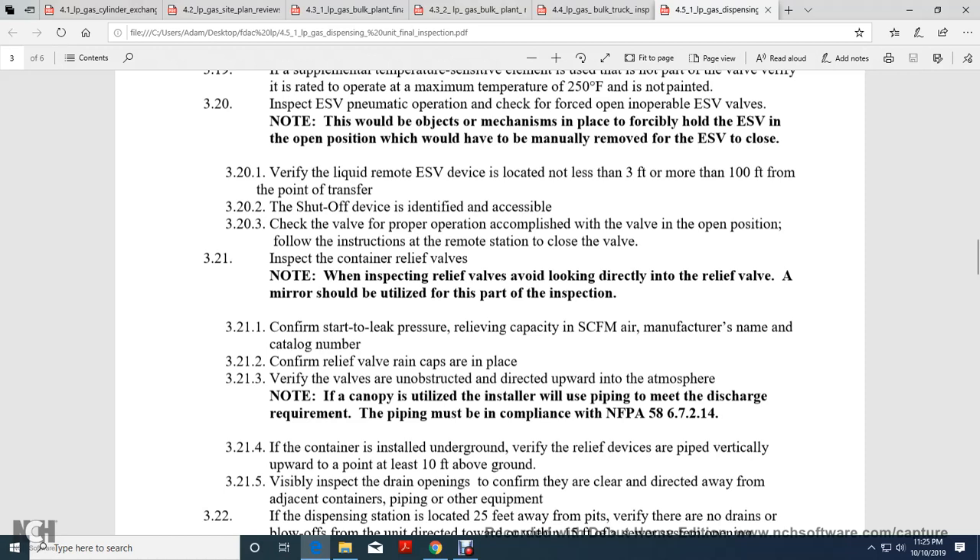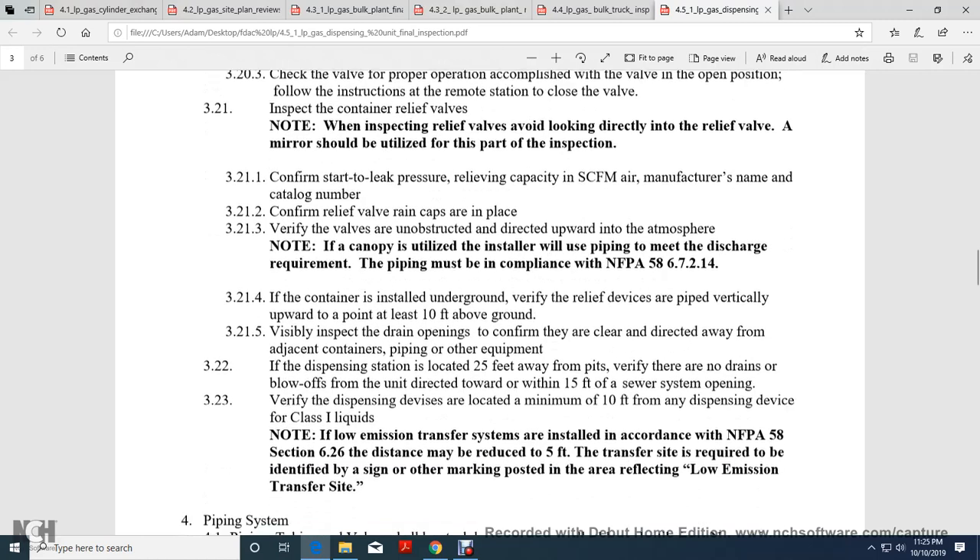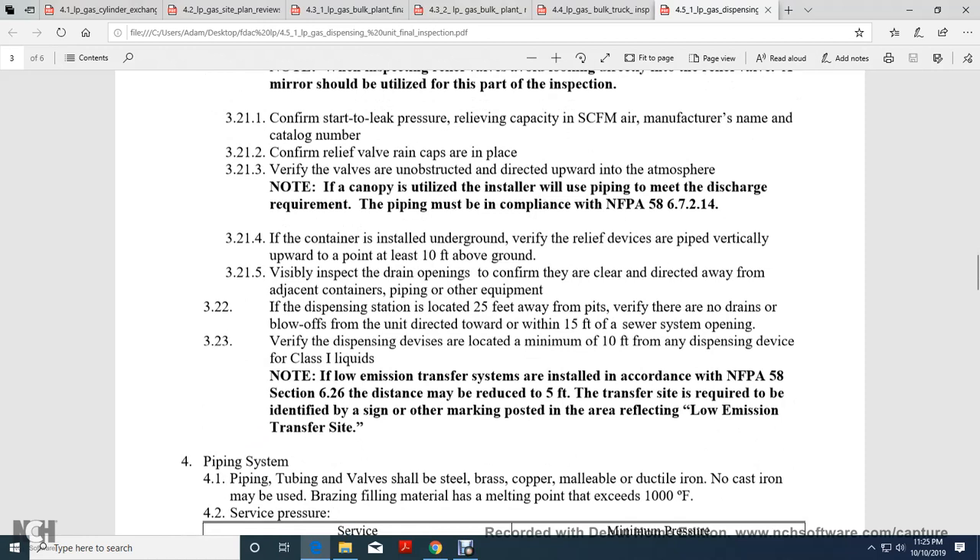Note: When inspecting relief valves, avoid looking directly into the relief valve. Mirrors should be used for part of the inspection. Confirm start-to-leak pressure, relieving capacity in SCFM, air manufacturer's name, and catalog number. Check that relief valve rain caps are in place. Verify that valves are directed upward to the atmosphere. Note: if a canopy is utilized, the installer will use piping to meet the discharge requirement; piping must comply with NFPA 58 6.7.2.14.